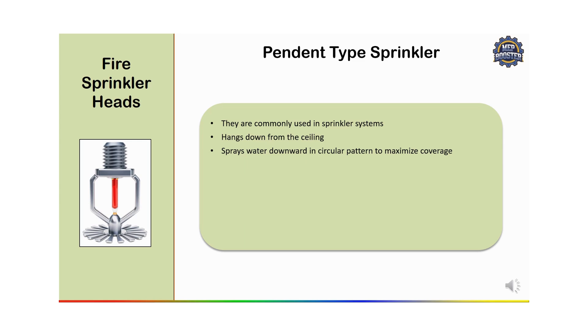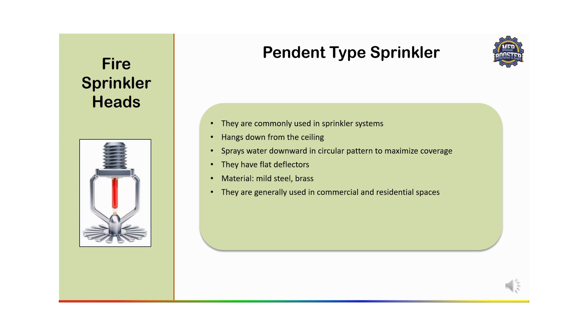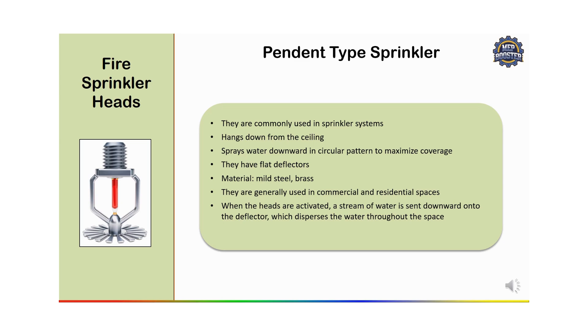The characteristics of pendant type sprinkler are that it provides broad coverage with a circular pattern. They have a flat deflector, normally made of mild steel or brass. They are generally used in commercial and residential spaces, and are ideal for offices, hotels, and factories.